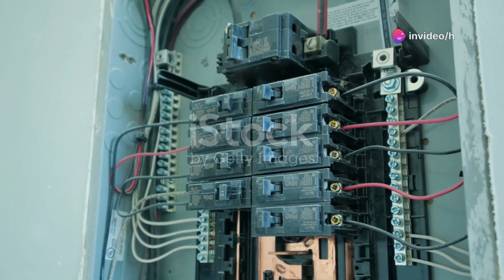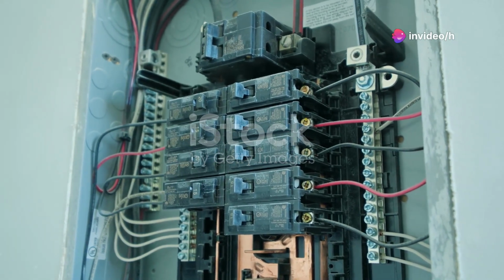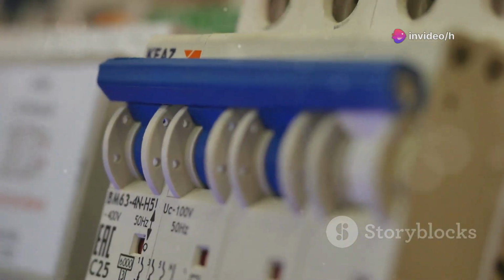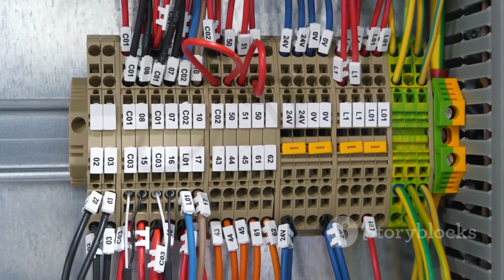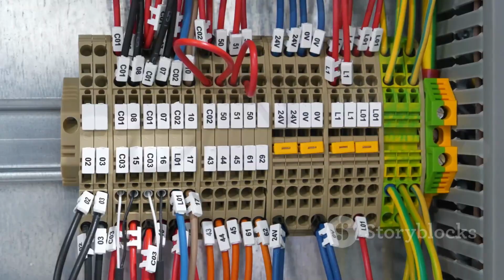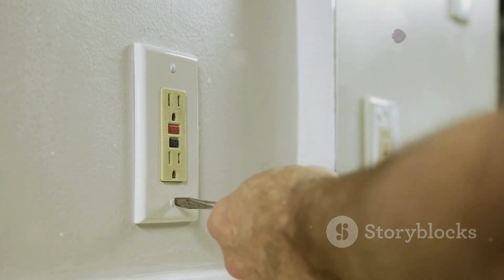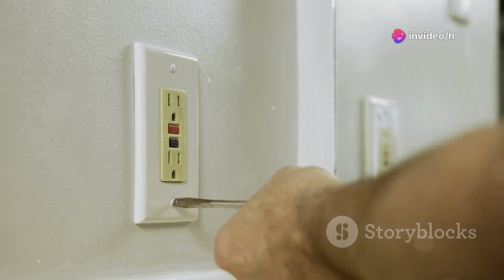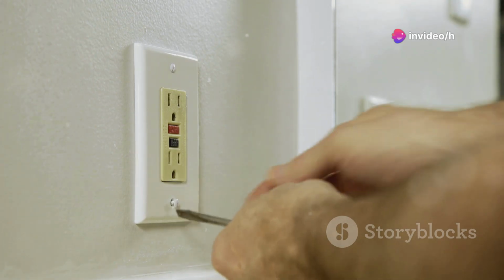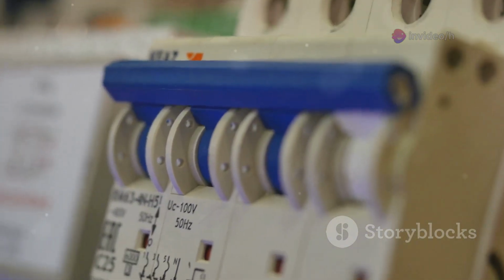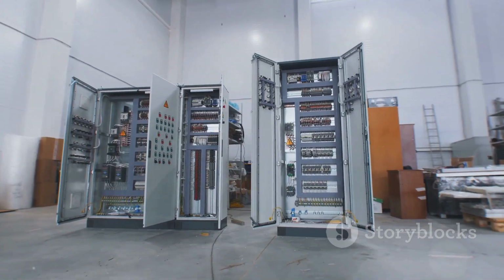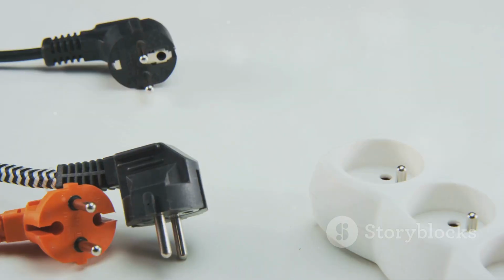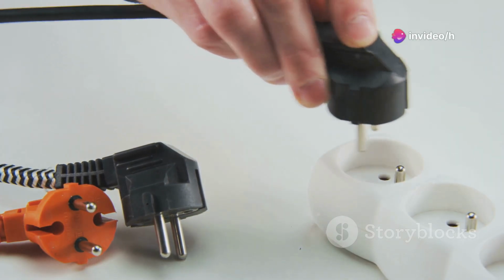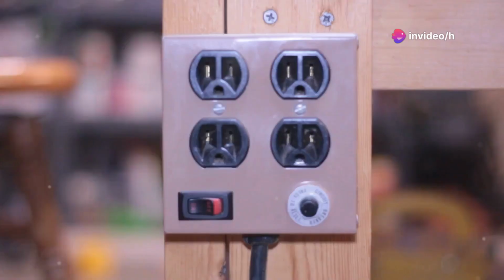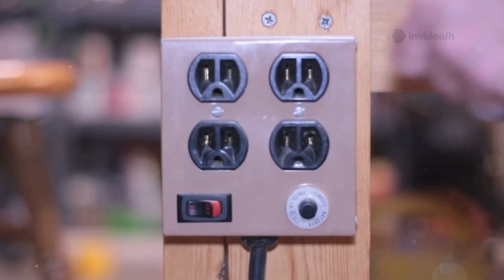The split-phase system gives us both 120V and 240V using the same wires. Inside your panel, two hot bus bars, leg A and leg B, and a neutral bar make it all work. Standard circuits use a single pole breaker, connecting one hot leg and neutral for 120V, perfect for lights and outlets. For big appliances, a double pole breaker connects both hot legs, delivering 240V. Some 240V appliances also need a neutral for controls or lights, so they get 4 wires: 2 hots, 1 neutral, 1 ground. This setup powers everything from your phone charger to your oven.